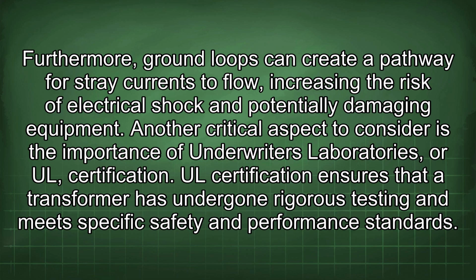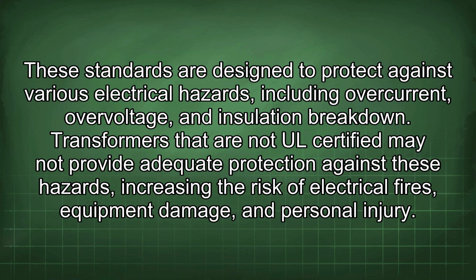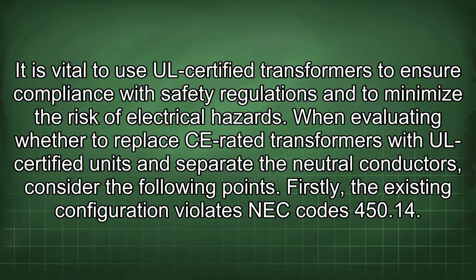Another critical aspect to consider is the importance of Underwriters Laboratories, or UL, certification. UL certification ensures that a transformer has undergone rigorous testing and meets specific safety and performance standards. These standards are designed to protect against various electrical hazards, including overcurrent, overvoltage, and insulation breakdown. Transformers that are not UL certified may not provide adequate protection against these hazards, increasing the risk of electrical fires, equipment damage, and personal injury.